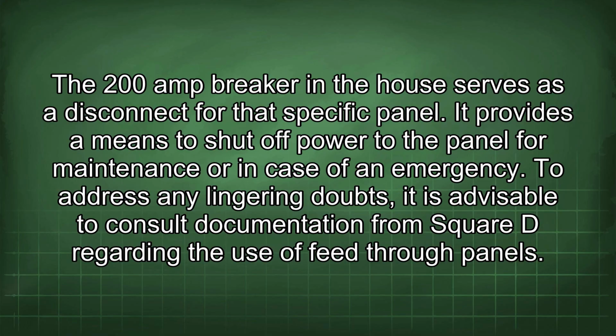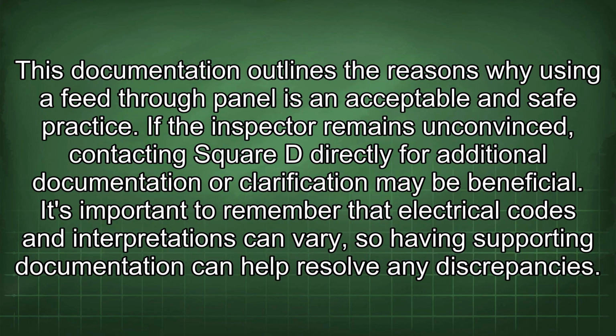To address any lingering doubts, it is advisable to consult documentation from Square D regarding the use of feed-through panels. This documentation outlines the reasons why using a feed-through panel is an acceptable and safe practice. If the inspector remains unconvinced, contacting Square D directly for additional documentation or clarification may be beneficial. It's important to remember that electrical codes and interpretations can vary, so having supporting documentation can help resolve any discrepancies.